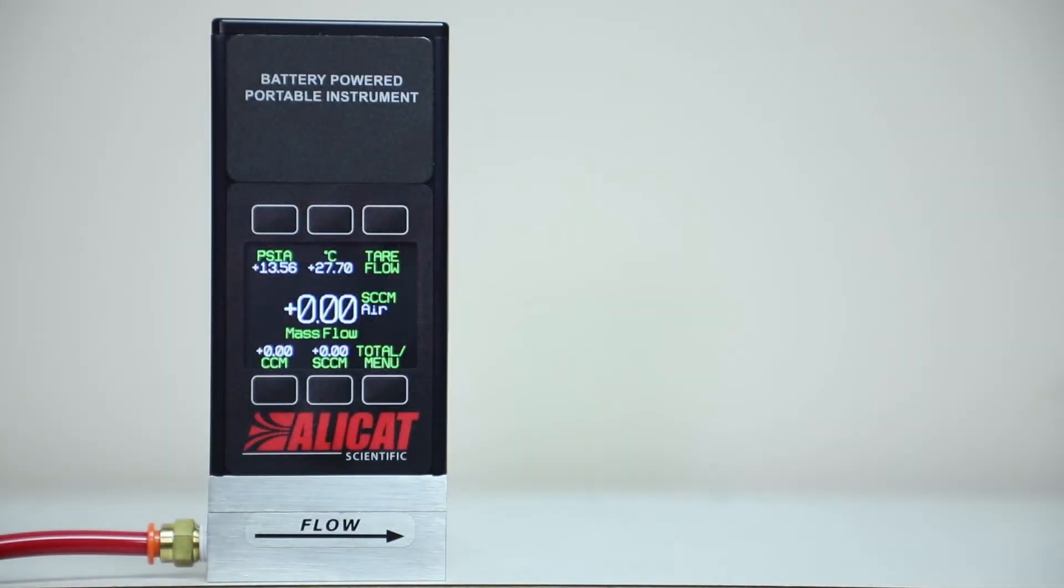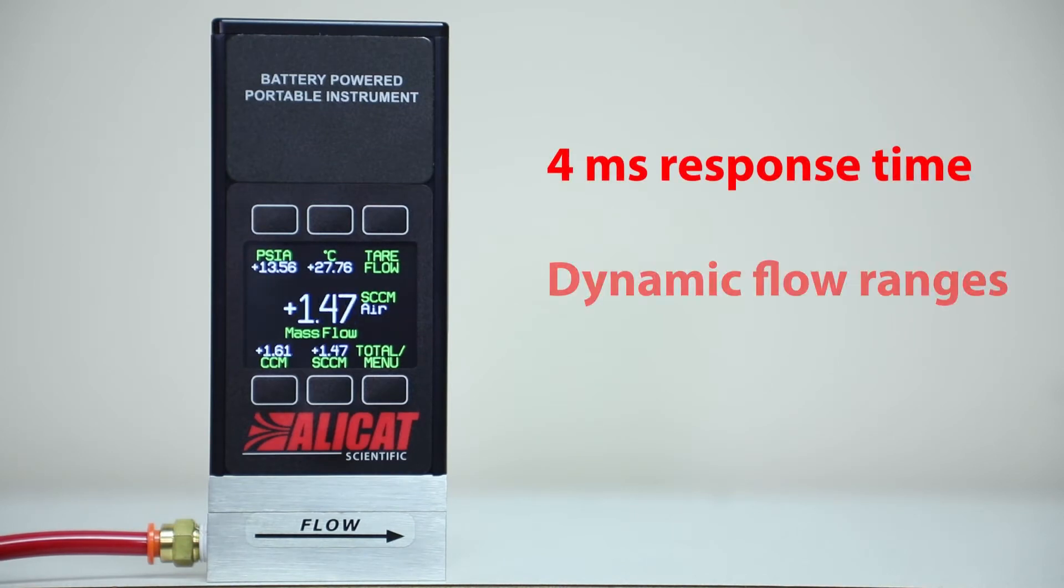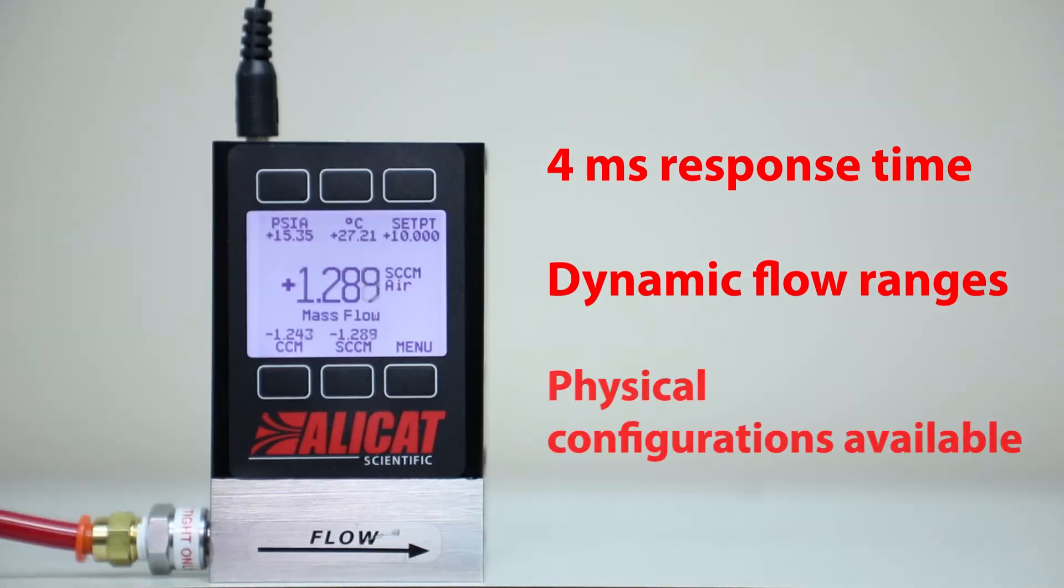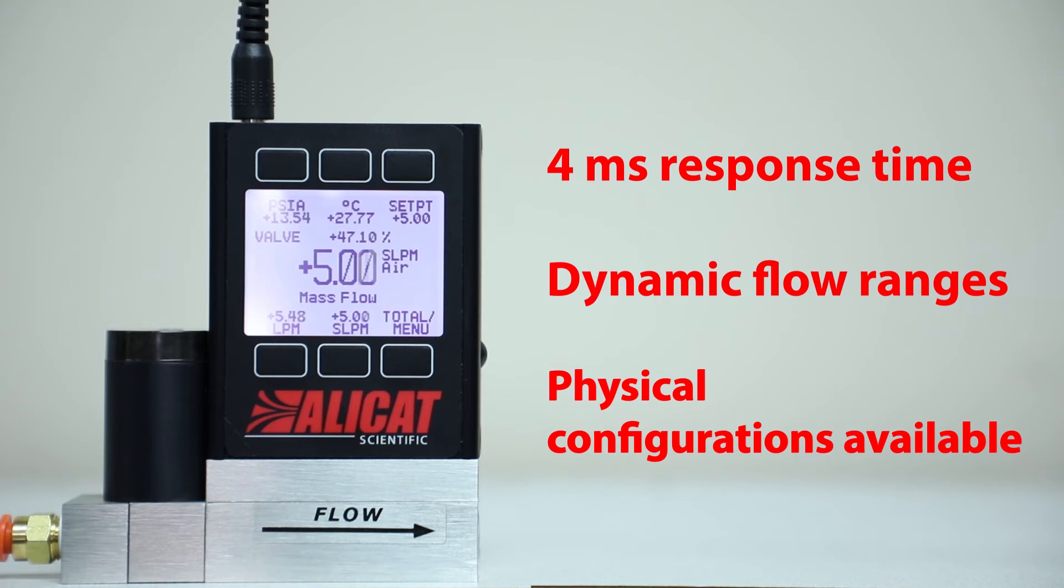Differential pressure-based flow measurement responds near instantaneously and allows for wide, dynamic flow ranges. With many physical configurations available as well, it is easy to get your project up quickly.